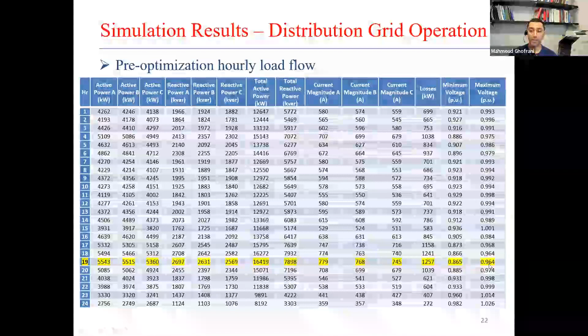And you can also see that the minimum voltage is now increased to 0.963 per unit from what it used to be, 0.865 per unit. So that's an improvement in the minimum voltage, and you also have an increase in the maximum voltage. As you can see, the maximum voltage is now 1.027 per unit compared to what it was before the optimization, which was 0.964 per unit. So if I go back to the post-optimization result, the minimum and the maximum voltage are well within the 0.95 and 1.05 per unit acceptable standard range.